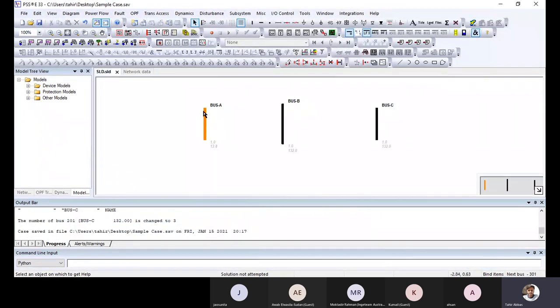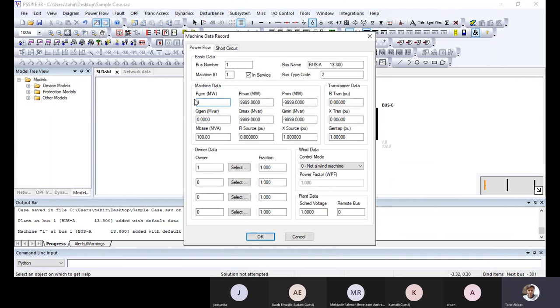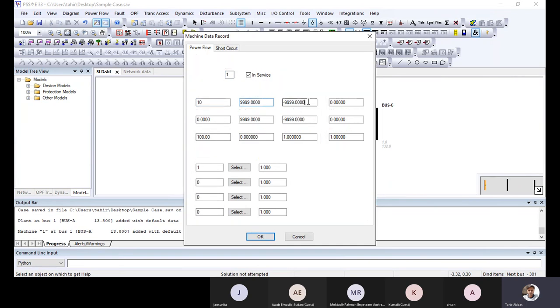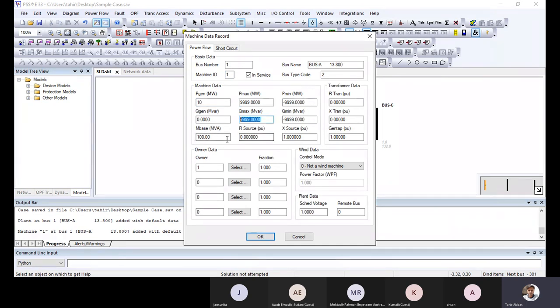So now, because we have made this a generator bus, we need to add a generator on this bus. This is a 10 megawatt generator, with P max and P min, Q max and Q min, and the MBase. These are given based on the reactive capability curve of a generator. There is no hard and fast rule to calculate these things. Basically, that is called the generator capability curve. It tells us that if you are producing this much megawatt, in order to keep MVA constant, this much reactive power you can produce.